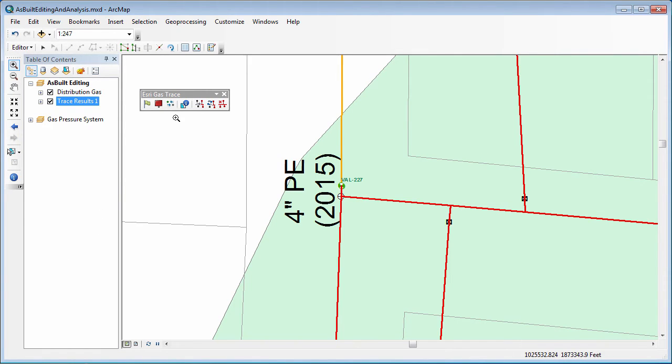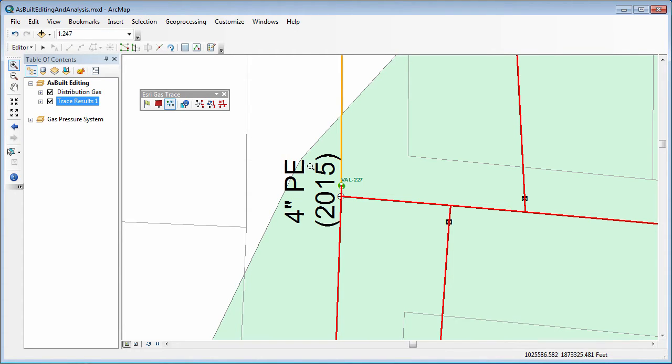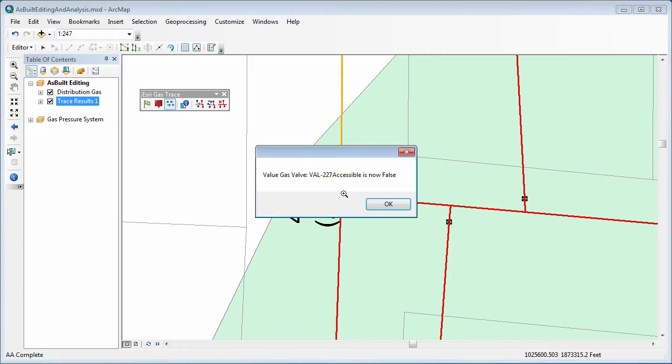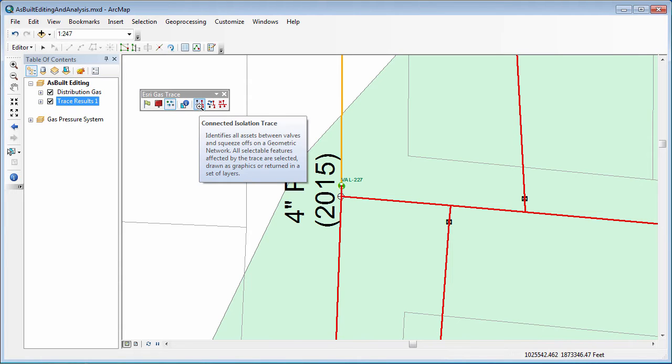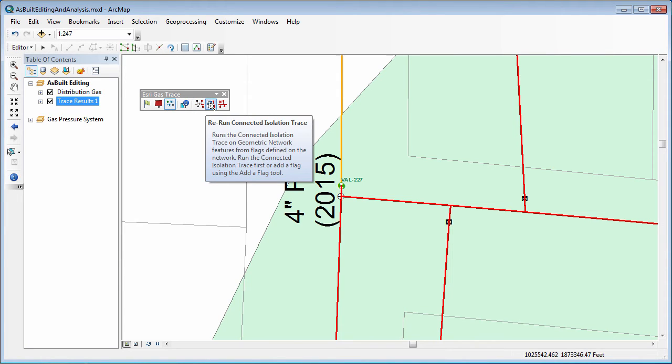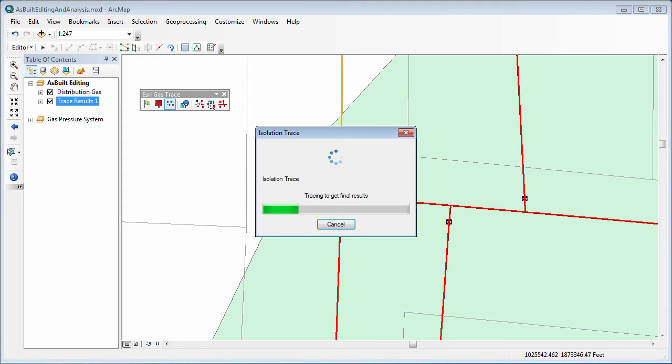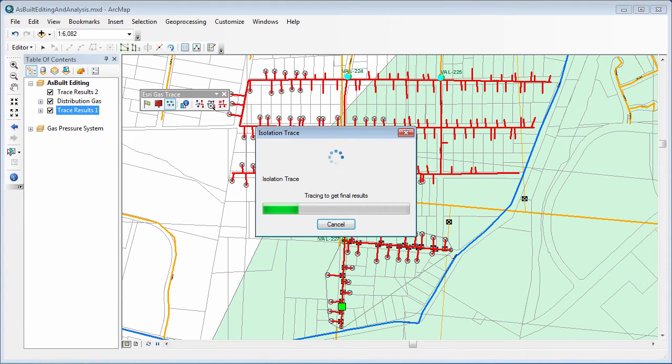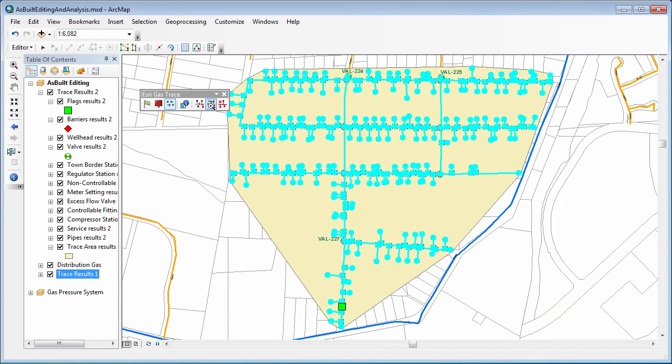What I'm going to do now is actually utilize a tool here on the toolbar, which is change the operable status of a valve. As I go ahead and click on this valve, notice it's now flipping the field accessible over to false, indicating that that valve is no longer accessible. So we're using fields behind the scene to drive that functionality. But with that change, I can now rerun the trace just as I ran it before. I'll use the same components of the trace that I ran the first time and find new results. And you can see here now it's a much larger area on the map.